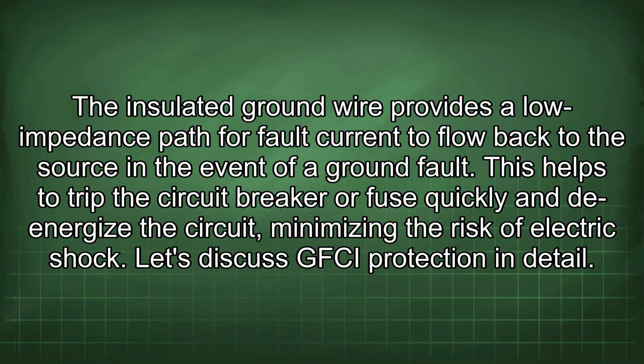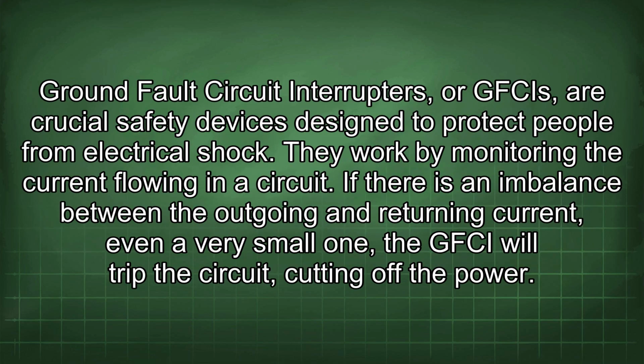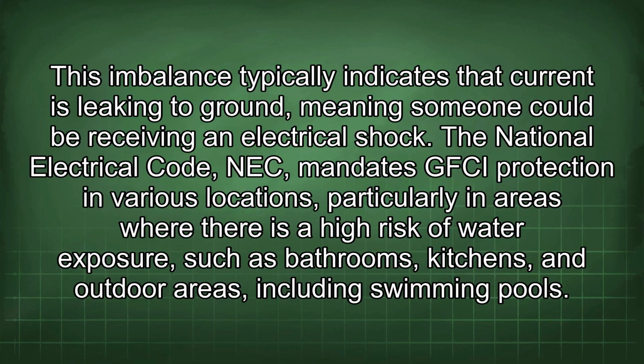Let's discuss GFCI protection in detail. Ground fault circuit interrupters, or GFCIs, are crucial safety devices designed to protect people from electrical shock. They work by monitoring the current flowing in a circuit. If there is an imbalance between the outgoing and returning current, even a very small one, the GFCI will trip the circuit, cutting off the power. This imbalance typically indicates that current is leaking to ground, meaning someone could be receiving an electrical shock. The National Electrical Code (NEC) mandates GFCI protection in various locations, particularly in areas where there is a high risk of water exposure, such as bathrooms, kitchens, and outdoor areas, including swimming pools.